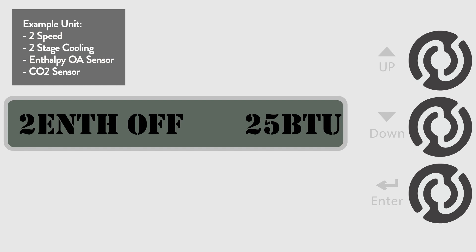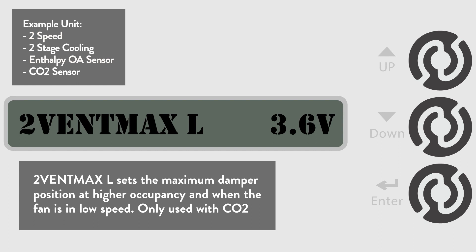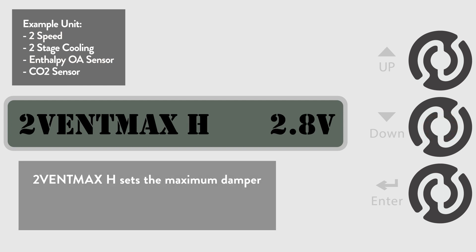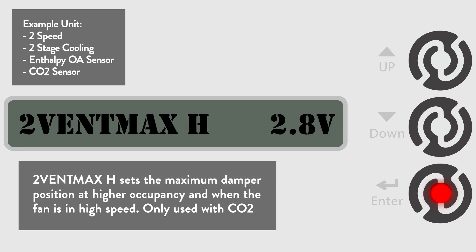Go to the 2 Vent Max L menu to set the CO2 sensor's maximum non-free cooling position when the unit is in low speed. The default is 3.6 volts, but let's change that to 3.4 volts. Go to the 2 Vent Max H menu to set the CO2 sensor's maximum non-free cooling position when the unit is in high speed. The default is 2.8 volts, but we are going to change that to 2.6 volts.